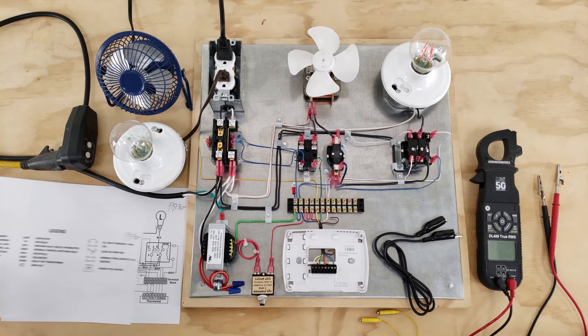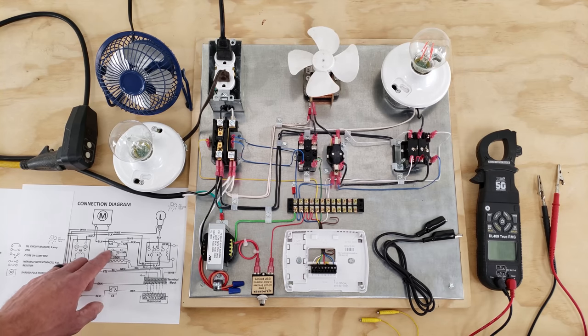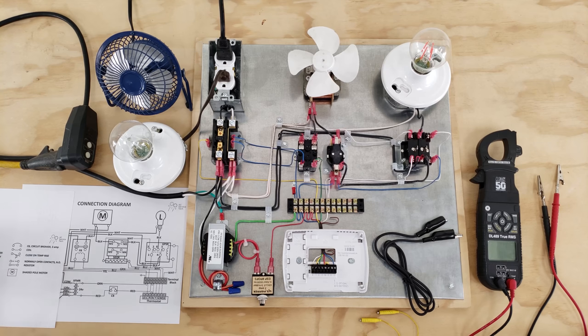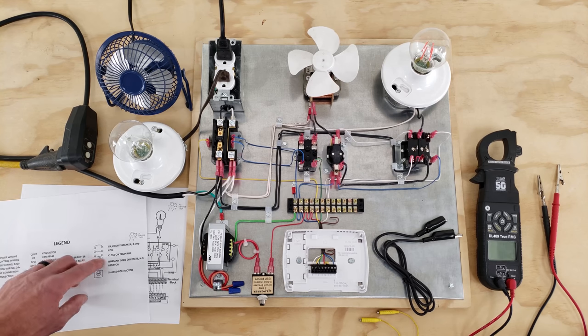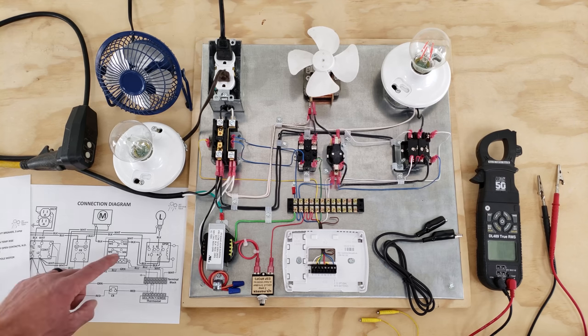And so that's why you have a switch right here. And then you also see that it's based on temperature. The fact that this is open right now between this point and this point, and that it's going to take a temp rise for it to close, you can see that it's a close on temp rise. And so right here you have on your legend, close on temp rise. This is typically used for temperature sensors, but in this case, we included it on the sequencer.